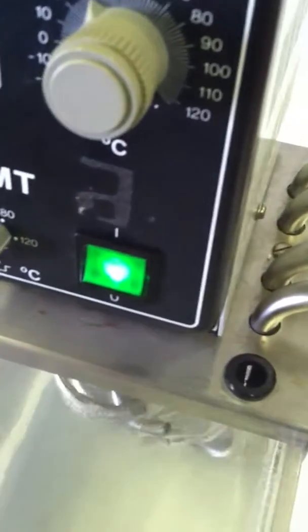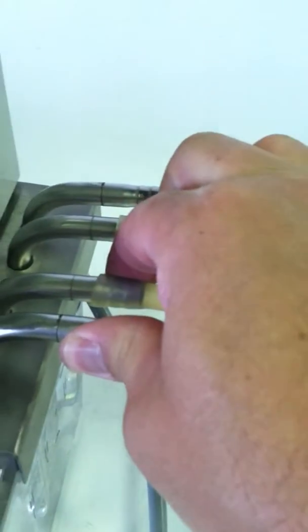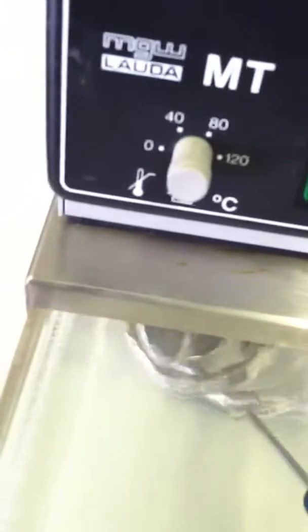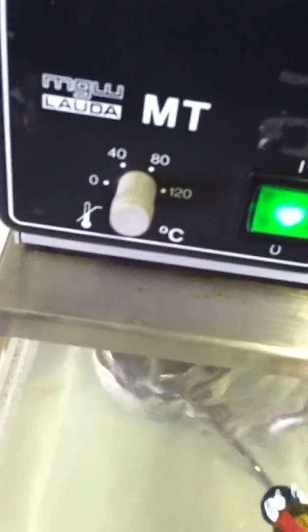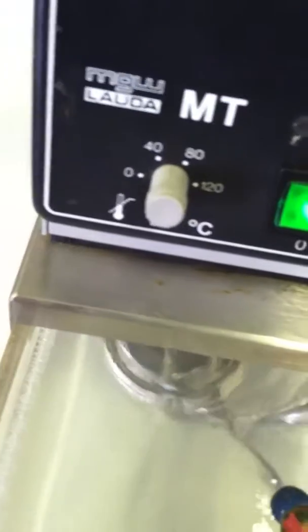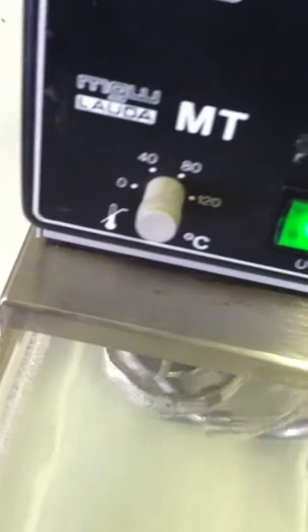That little rattling sound is just vibration. If I depress this a little bit, you'll hear it go away. When you get these baths, the position of the motor down here and the impeller can cause it to make a little noise, but by shifting it one or two times, or maybe tying that up, it becomes very quiet and works well.